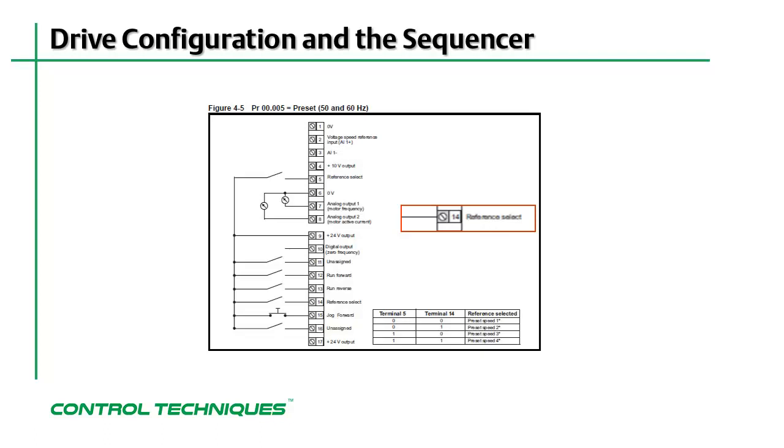Notice how the function of terminal 14 is now changed as compared to when the drive was in AV mode. That's why it's important to have a knowledge of the relationship between menu 0, parameter 5, and the drive sequencer.